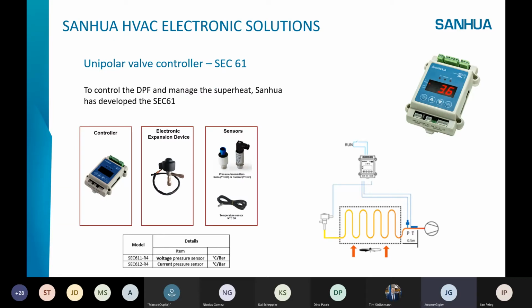To control this unipolar valve, Sanhua developed the SEC 61. The SEC is a Sanhua electronic controller. It is able to control the unipolar valve, but to control the superheat of the installation at the evaporator, you also need a temperature sensor and a pressure transmitter to calculate the superheat. So pressure transmitter and temperature sensor at the outlet of the evaporator. The controller measures and calculates whether it needs to open or close the valve depending on the superheat setting. You also need a run signal to start or stop the control of the superheat. Mainly it is in parallel with the on-off of the compressor.